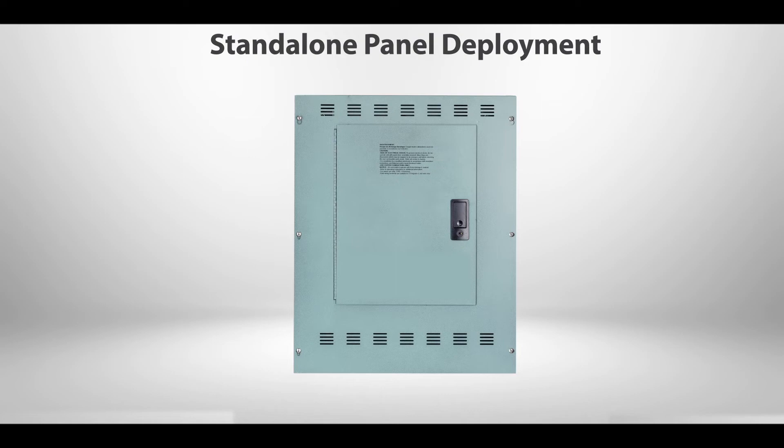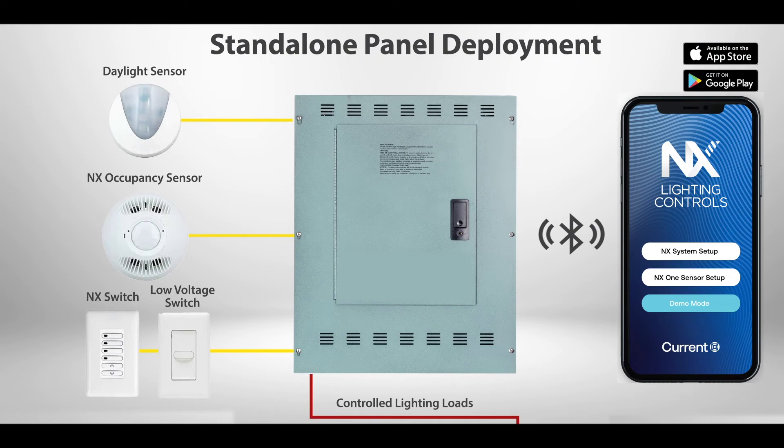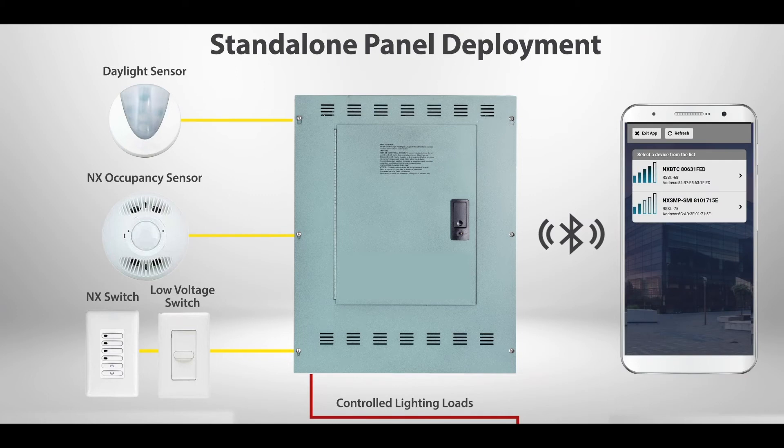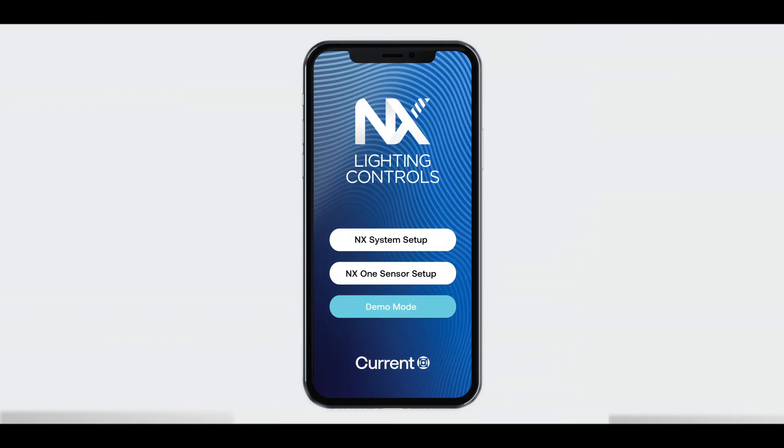The NX panel is designed to operate as a standalone panel or as a connected device on the NX Lighting Control System HubbNet network. To program a standalone panel: 1. Download the HCS Control Hub app, available in Android and iOS versions from Google Play or the Apple Store. 2. Plug an NX Bluetooth radio bridge into one of the panel smart ports. 3. From the Control Hub app, select NX System Setup. A page will show all NX Bluetooth devices in range. 4. Select the panel. Once a Bluetooth connection has been made, the app will display a list of the panel relays, dimmers, and devices available for programming. Program devices and schedules according to the Control Hub app Quick Start User Guide.